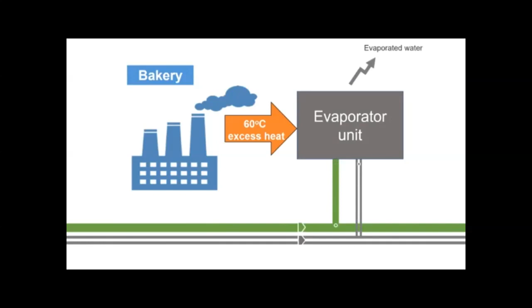An energy source, in this case a hot exhaust vent from a bakery, will be used to recover the liquid desiccant. Using an evaporator unit, the weak fluid is heated at relatively low temperatures, in this example 60 degrees Celsius. Some of the water carried in the fluid will evaporate, leaving a stronger liquid desiccant water mixture.